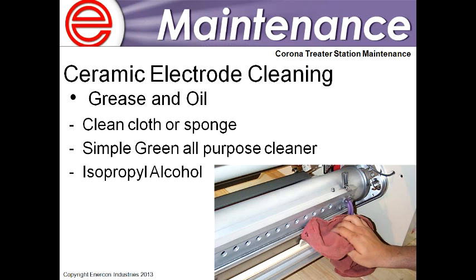And following up on that point, when I mentioned earlier in this presentation customers not having a well-planned maintenance schedule, or not cleaning all the right areas, this image right here is the first image that pops into my head. I'll see a lot of people who mean well clean the face of the electrodes without hinging it open, but then they won't get in there and clean out, say, the brown insulating shroud that houses the electrodes. It's just a quick blow out with oil-free compressed air and a clean rag. That's the mental image I get when I think of people not cleaning all the right areas; they're just not getting back behind the electrodes.